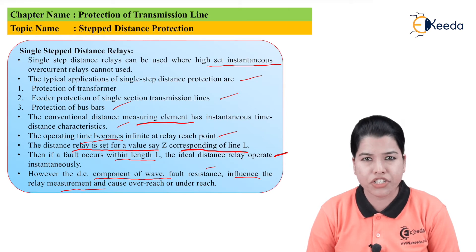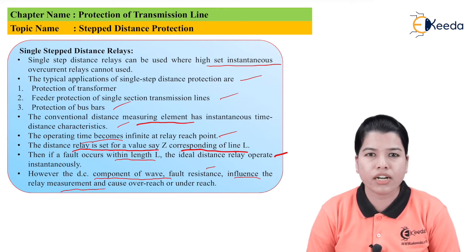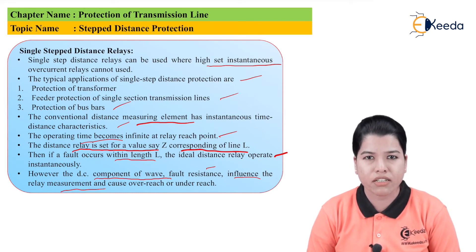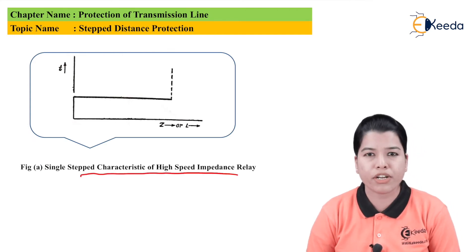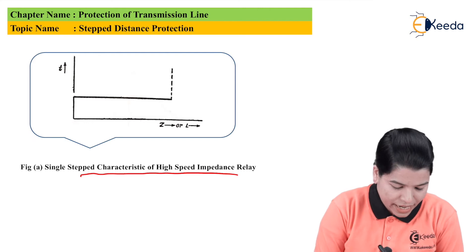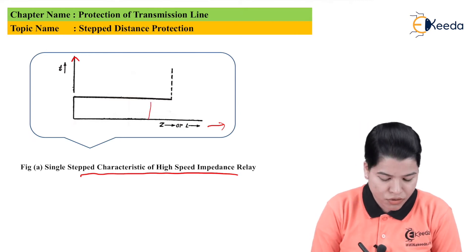In the case of overreach, the relay operates even when the fault has occurred outside its zone of protection, that is, outside the length L. That condition is called the overreach condition. Whereas in the underreach condition, the relay does not operate even if the fault has occurred within the length L. So practically, the relay might be inoperative or it might operate for faults outside or inside the zone. The figure shows the single step characteristic for high-speed operation of impedance relays, plotting time versus impedance or line length.